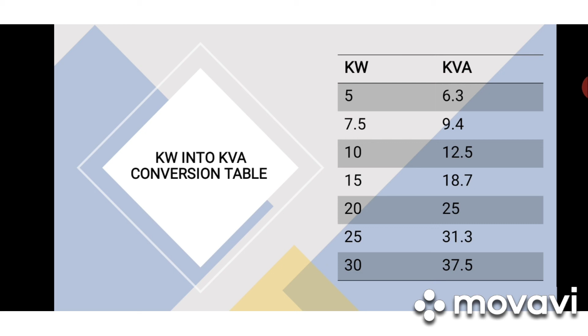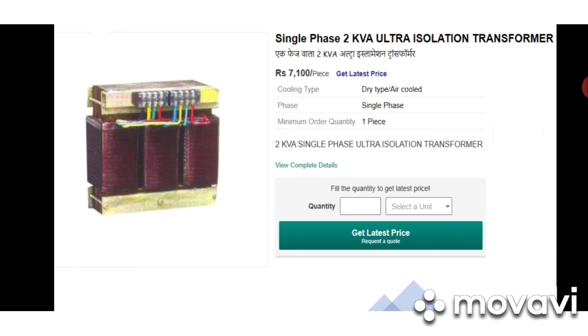Then you can see this chart. Suppose you are using only 5 kilowatts, then you need a 6.3 kVA transformer. Then you have to purchase a transformer accordingly, based on how much kVA you require.